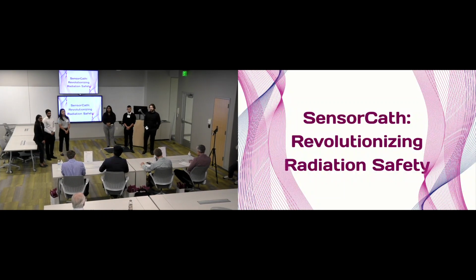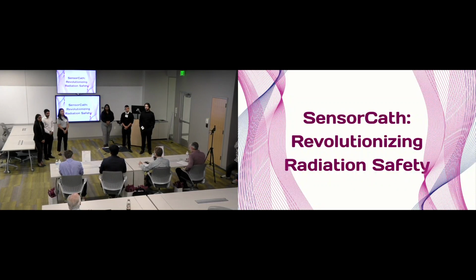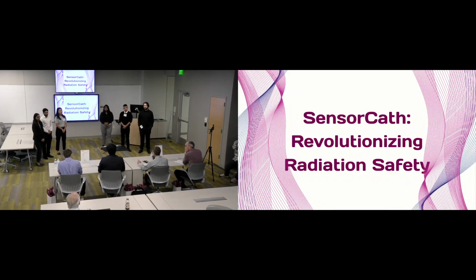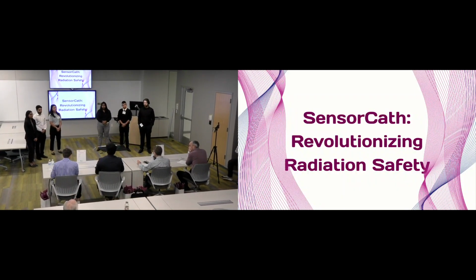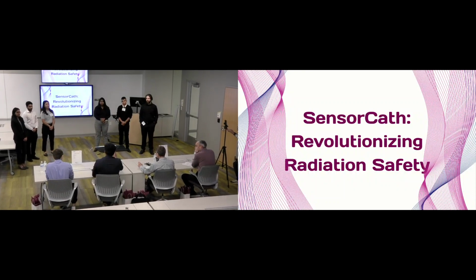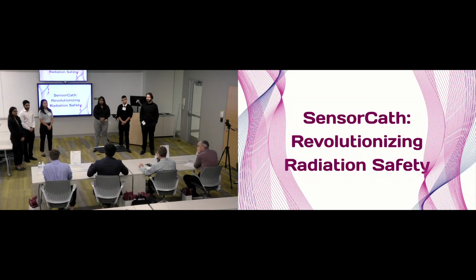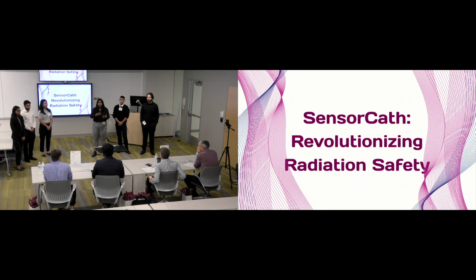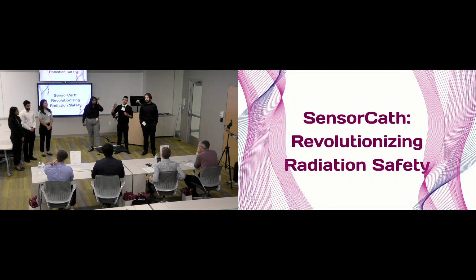So you are talking about a clot that a physician is trying to reach, and so we are talking two things. When you are talking distance, they are using the existing lead apron they use now. We are working farther from the table. Right. That's the concept, fine. We want to decrease the amount of lead in the protection. The further they are, the less lead protection they need. Ideally, we haven't done the exact numbers, but at least 50%, depending on how far away they are. It's supposed to go from currently 22 pounds, and we are aiming to reduce that to 10 pounds.